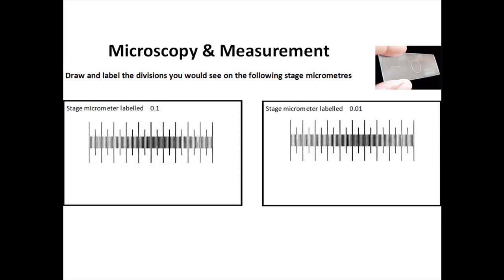We do that using one of these — a stage micrometer. A stage micrometer is essentially just a little ruler. So basically what we're doing is looking down the microscope and putting a ruler underneath it. When we look at the ruler, if one unit on the eyepiece graticule is equivalent to one millimeter on the ruler, then whether we put it on low, medium, or high power doesn't matter, because even though the millimeter is going to look bigger, it's still going to read as one millimeter. So basically, we're putting a ruler under the microscope to establish what one unit on our eyepiece graticule actually is worth. A stage micrometer is, like I said, essentially a ruler, and just like your plastic ruler which has smaller units — maybe millimeters and centimeters — we've got the same thing here.